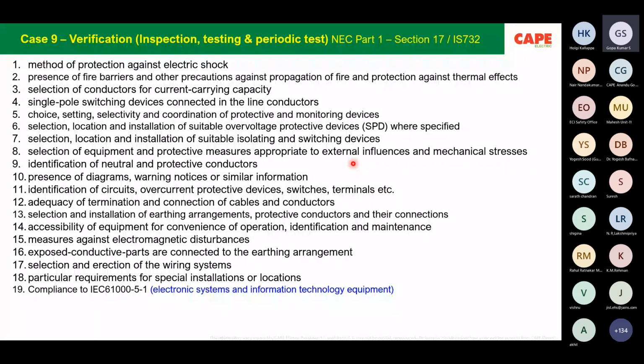Verification is nothing but inspection and testing. We can simply call it auditing, or auditing is actually not the correct word. Auditing is a sampling process. You have 100 circuits and you select maybe 2-3 circuits and make an audit, which is not correct. At least once, you must do a verification of all the circuits. Here, verification consists of inspection and testing. There are 18-19 points for verification.